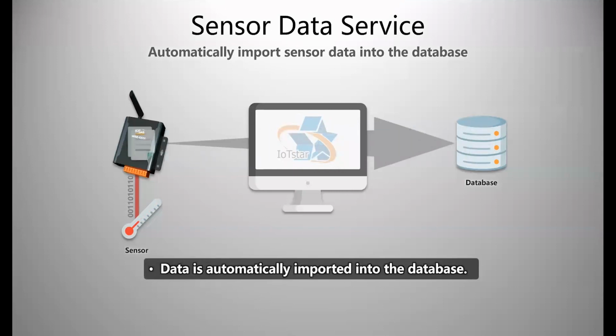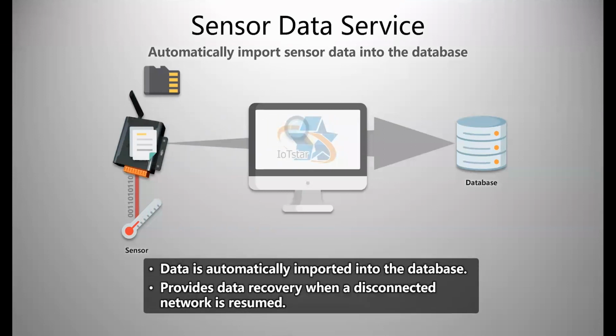One of the strengths of IoTstar is that it supports data logger. When the network is disconnected, the collected data will be stored in the edge controller's micro SD card. And when the network is resumed, all the data will be sent to IoTstar and be imported into the database.